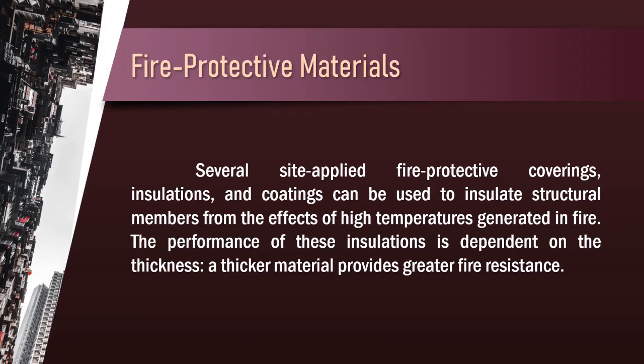Fire protective materials. Several site-applied fire protective coverings, insulations, and coatings can be used to insulate structural members from the effects of high temperatures generated in fire. The performance of these insulations is dependent on the thickness. A thicker material provides greater fire resistance.